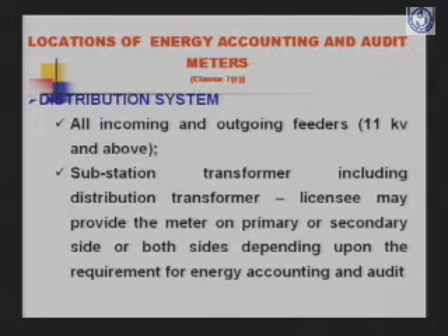They are generally being placed on the secondary side of the distribution transformer, and on both sides only when you want to calculate the losses of the distribution transformer. Otherwise they are placed only on the secondary side so that you can compare the energy supplied by the distribution transformer with the energy billed to the ultimate consumer. So that helps in accounting and auditing of energy supplied from a distribution transformer. Now it has become mandatory to provide meters on the distribution transformer as well. And in our country about 13% of the distribution transformers have been provided with meters.